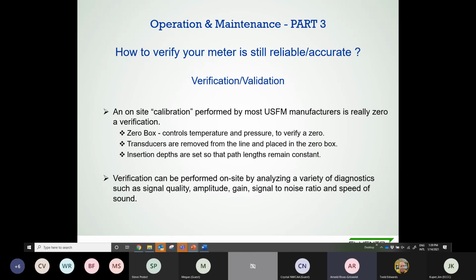You go there, you pull the sensors, put them in a zero box, and in that zero box, temperature is controlled, pressure is controlled, and there's no airflow. So you know that you're measuring air, so you know the composition of air, and you know the speed of sound of air, right? So you can compare that speed of sound with the speed of sound that you're measuring with your device. And at the same time, you control all the other elements, like, for example, the distance between the two transducers. That's something you have under control. You know that, and you fix those elements, and you get a good zero verification.